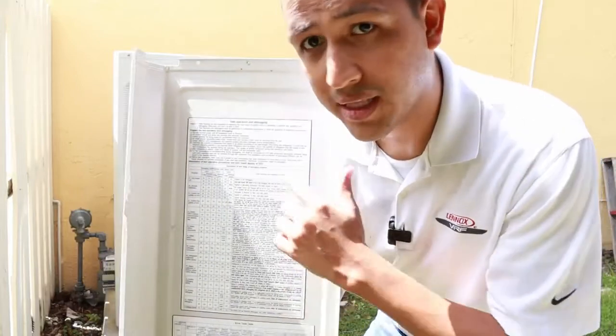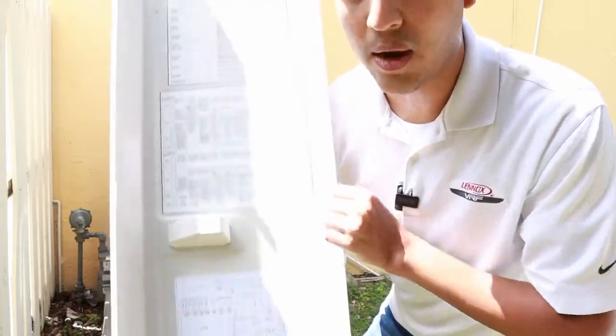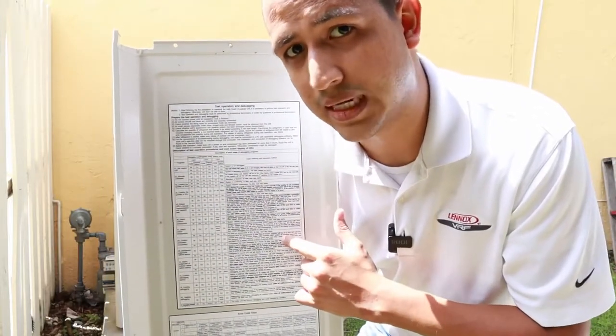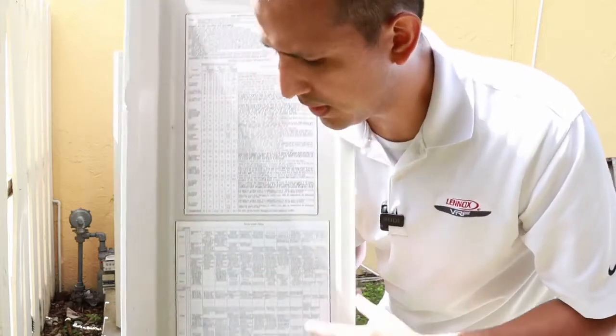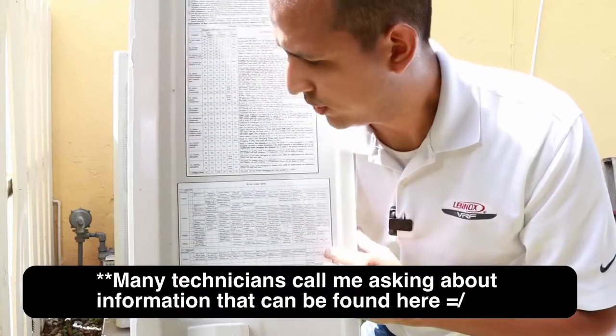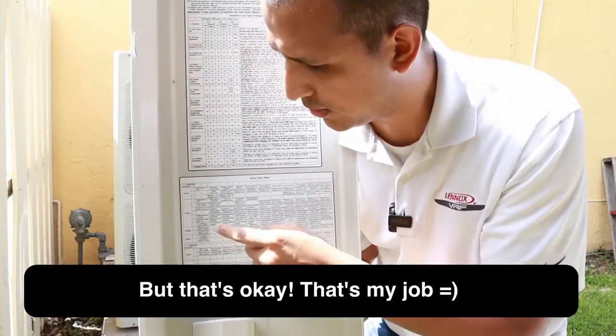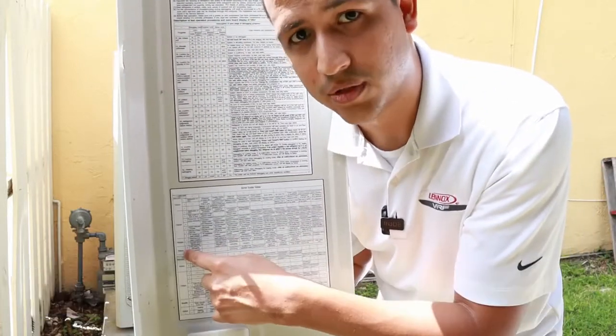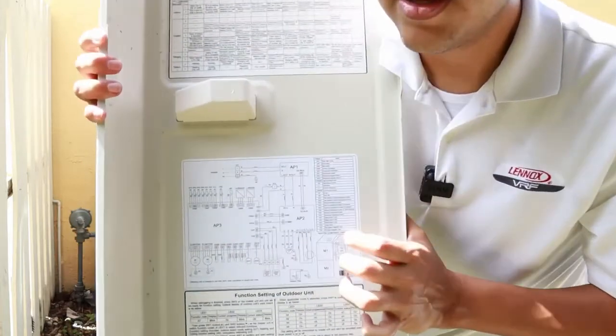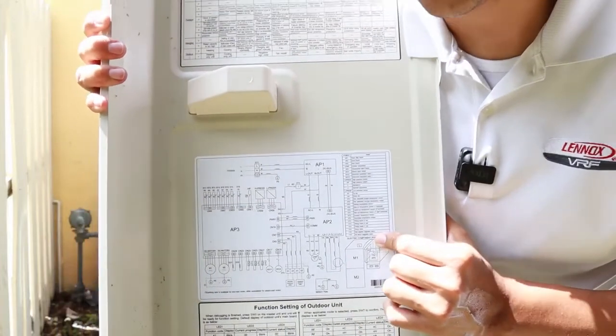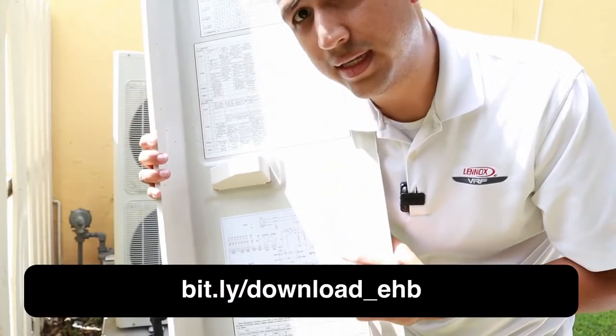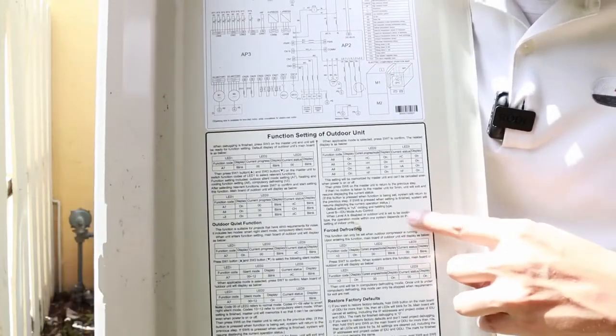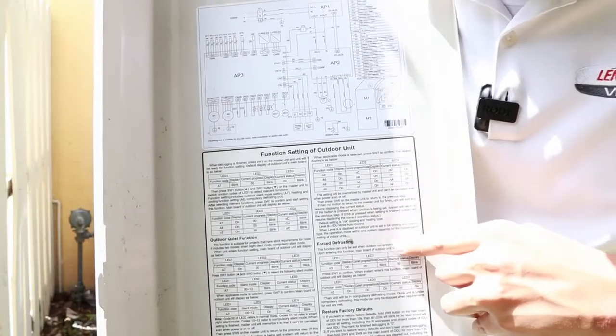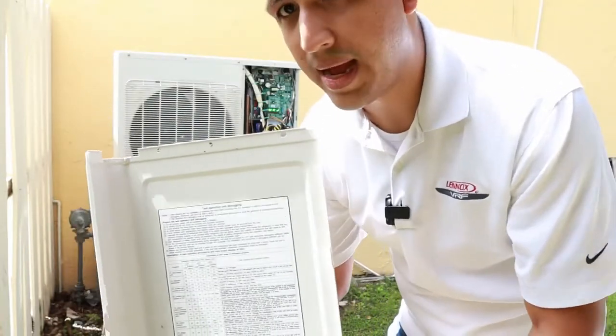Something very important to keep in mind: on the back of this panel, we have different stickers and labels you should keep in mind. At the top is the steps for the commissioning cycle, walking you step by step through how to perform it. The second sticker is a table for error codes, showing indoor unit codes, outdoor unit codes, commissioning cycle codes, and status codes. At the bottom is the wiring diagram, which I always recommend taking a picture of, although you can also find it in the engineering handbook. At the very bottom is a description of the different LEDs and settings we can adjust from the condensing unit using its buttons. Keep in mind there's a lot of information on the back of this panel.